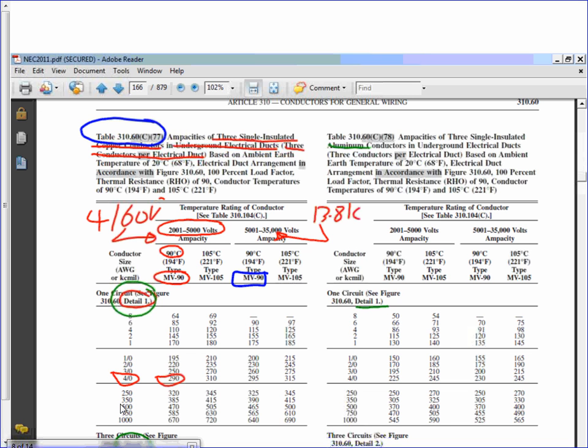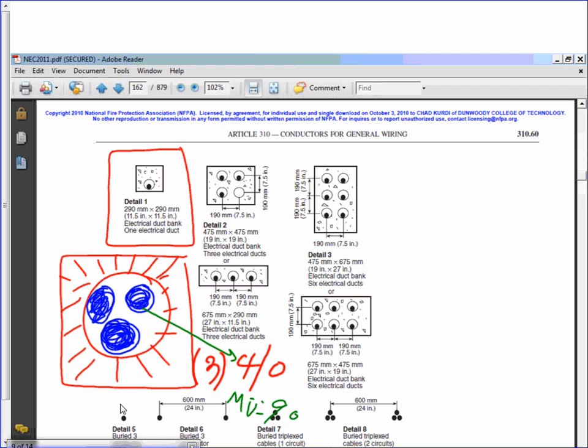Why didn't I go to the 105? See, you don't go to 105 until they tell you the cable is rated for 105. I didn't tell you anything. So you default to where? To the 90-degree column. Can you please write yourself a note of that? This is how they do it, guys.